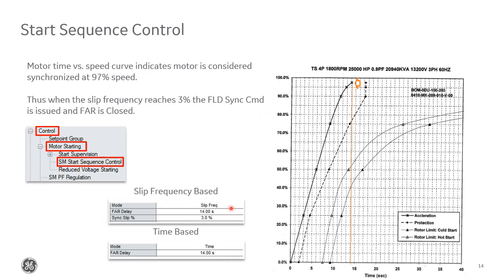If we select the mode to be slip frequency based, then we need to set the sync slip percent setting. This would be the slip at which the motor is considered synchronized. So we can look at the motor data sheets, for example, this one on the right. On the far left, we have the acceleration curve that shows the time versus percent of speed. At the very end point of this curve is when the motor is considered up to speed. So in this example, that's about 97%, which means our sync slip would need to be set to 3%.